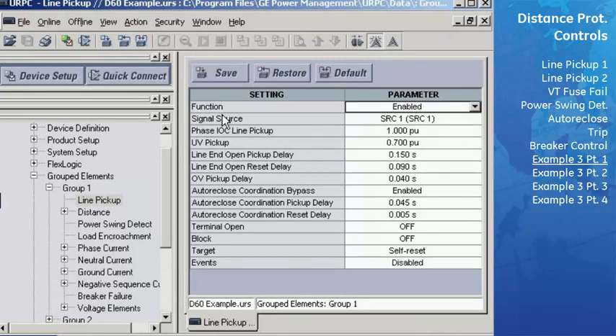Also, keep the line end open pickup delay as 150 milliseconds and the line end open reset delay as 90 milliseconds. This ensures that the line end open will be set well after the breaker has opened and will remain sealed in long enough for the line pickup to operate properly. Leave the overvoltage pickup delay at 40 milliseconds to ensure this will pick up after the breaker has closed. The auto reclose coordination bypass can be enabled since our transmission line is supplied by a strong source. The two auto reclose coordination timers will thus not be used and can be disregarded.